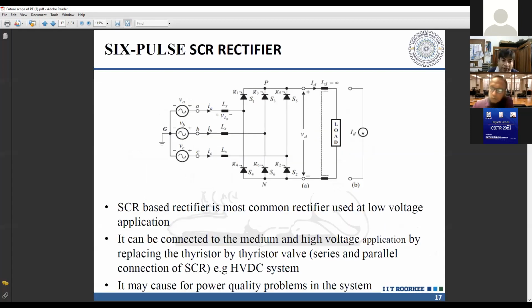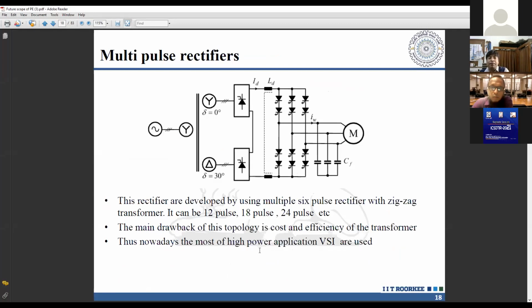Let's talk about the 6-pulse converter, which we've used since the first generation of power electronics in the 1970s. It's still used in HVDC systems, cascaded to handle huge voltages. But there's a power quality problem because it throws harmonics into the system—specifically 6n plus or minus 1 order harmonics into the source.